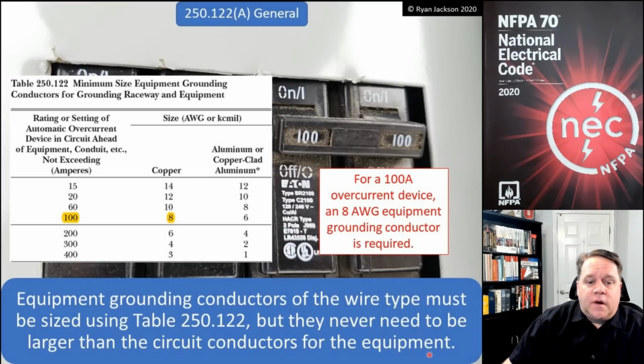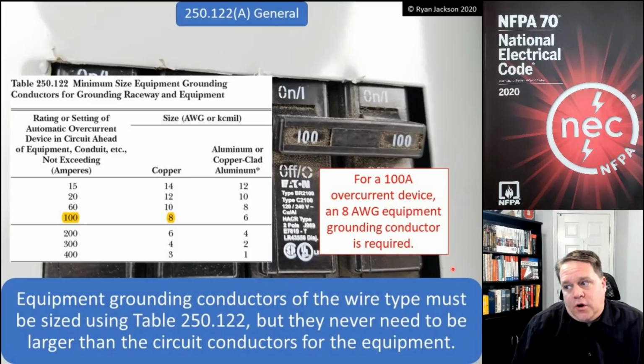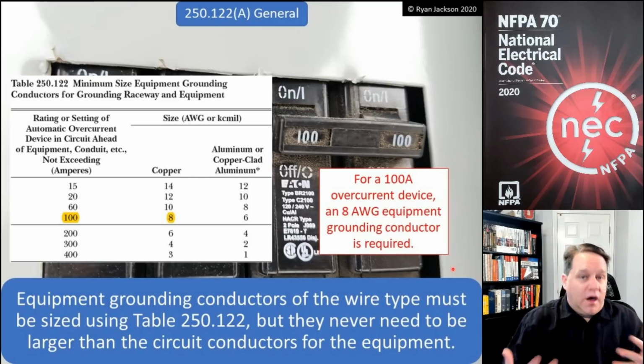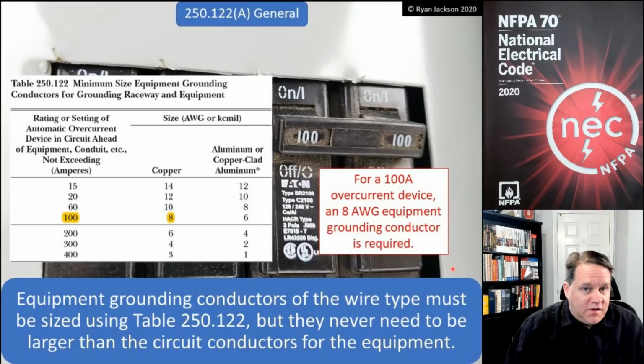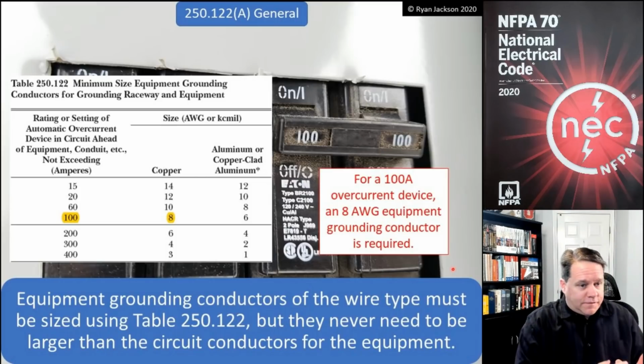So that's if I'm using an equipment ground of the wire type. You can still use a metal conduit as your equipment grounding conductor. You don't necessarily need a bare or green wire inside of your conduit if it's metal and it complies with 250.118. But for our discussion today, we're talking about sizing equipment grounding conductors of the wire type. So far it's nice and easy.